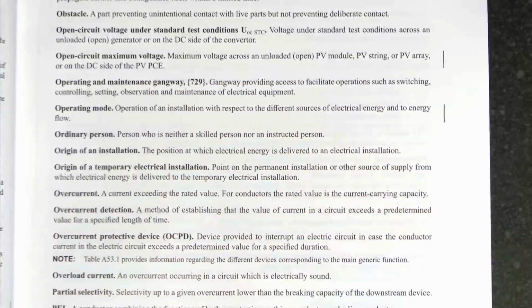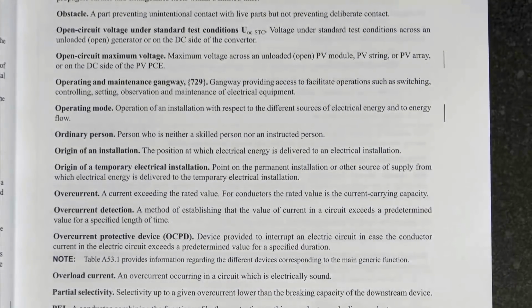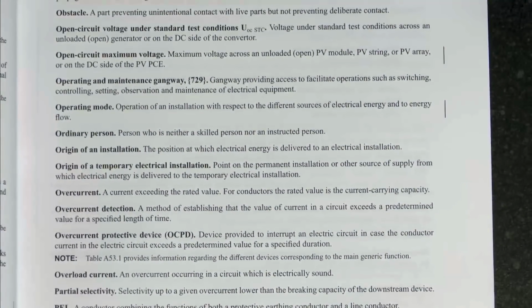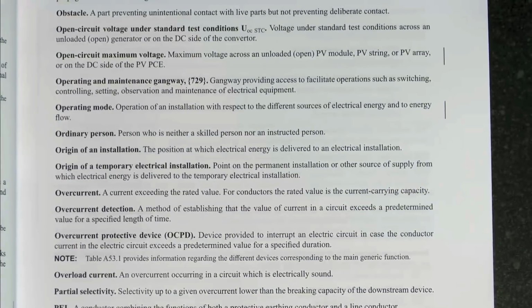Open circuit maximum voltage is the maximum voltage across an unloaded or open photovoltaic module, string or array, on the DC side. This again fits in with Part 8 and various newer technologies. Essentially, if you get a solar panel or set of panels on your roof and take the two ends of those wires with nothing connected, you're going to get a DC voltage there, and that's what open circuit maximum voltage is. If you didn't know, it could be many hundreds of volts.